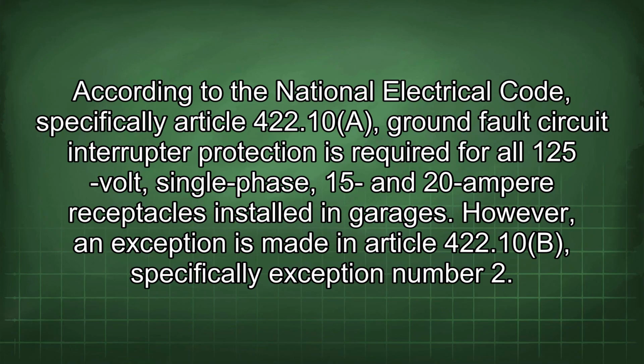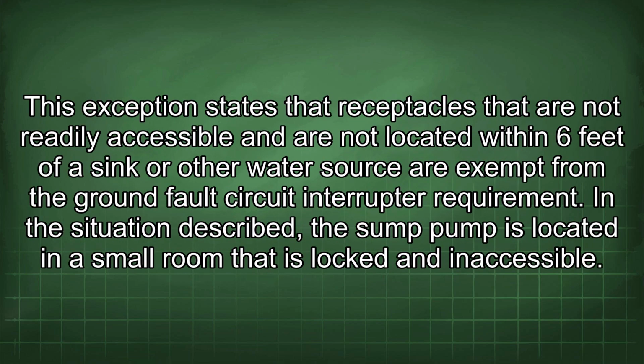According to the National Electrical Code, specifically Article 422.10a, ground fault circuit interrupter protection is required for all 125-volt single-phase 15 and 20 ampere receptacles installed in garages. However, an exception is made in Article 422.10b, specifically exception number 2. This exception states that receptacles that are not readily accessible and are not located within 6 feet of a sink or other water source are exempt from the ground fault circuit interrupter requirement.